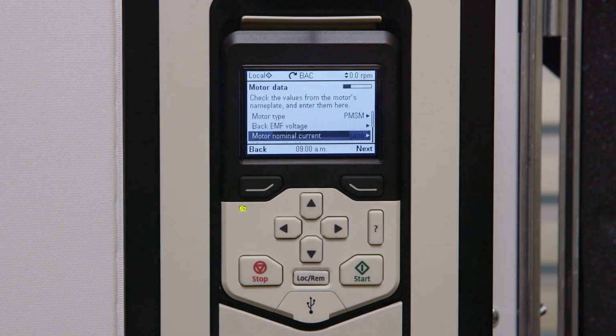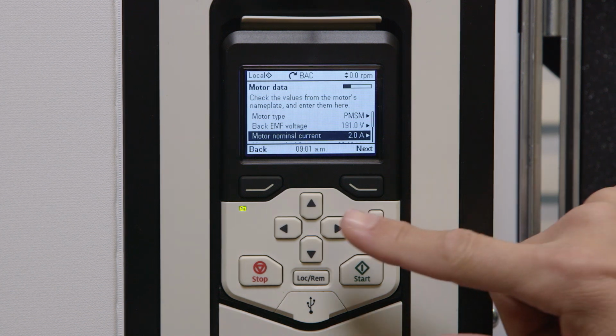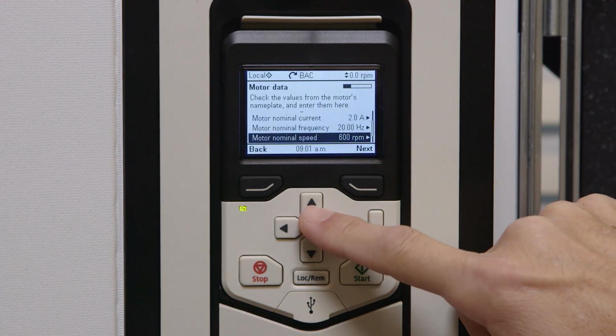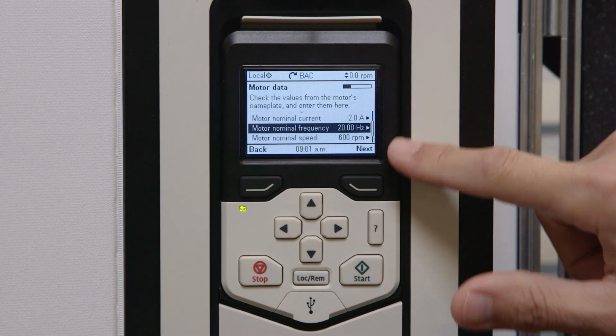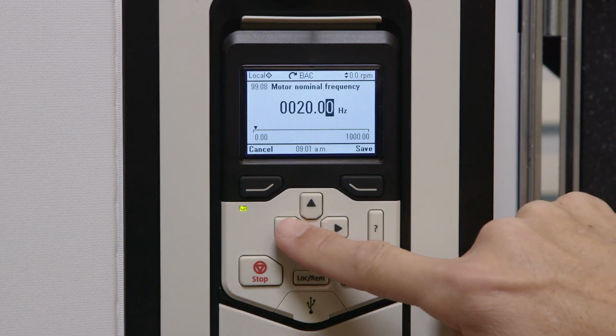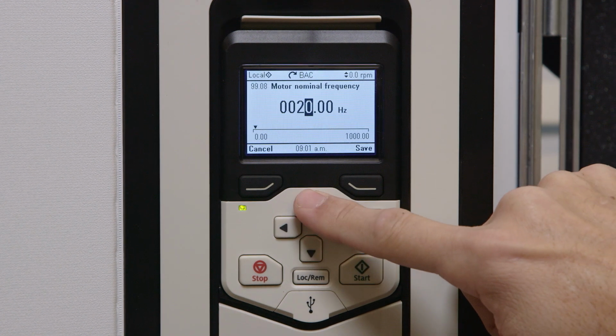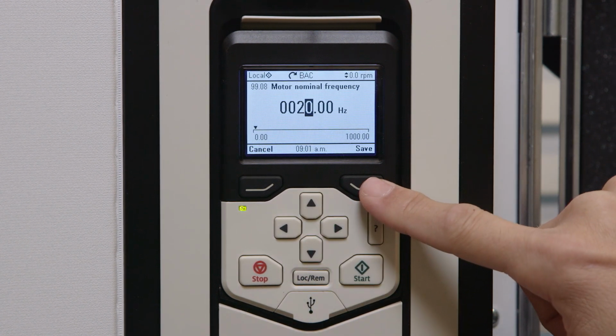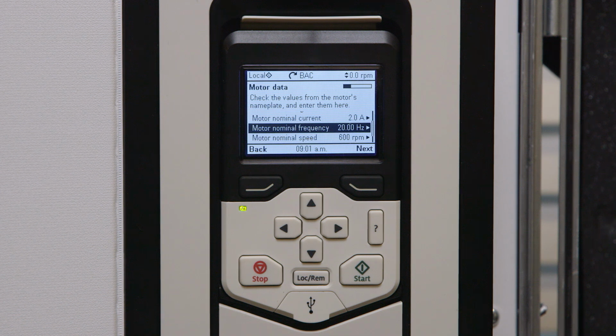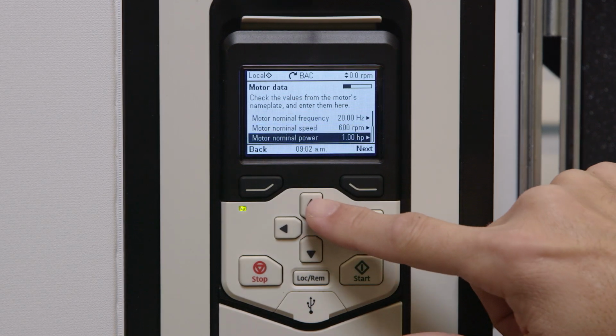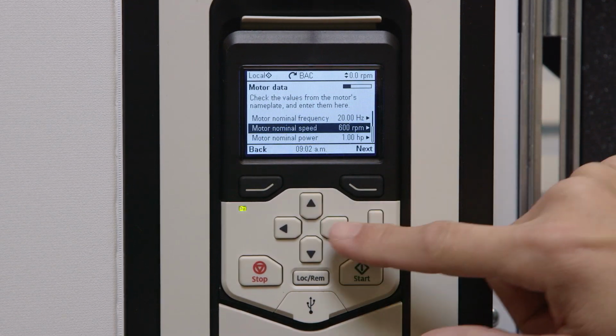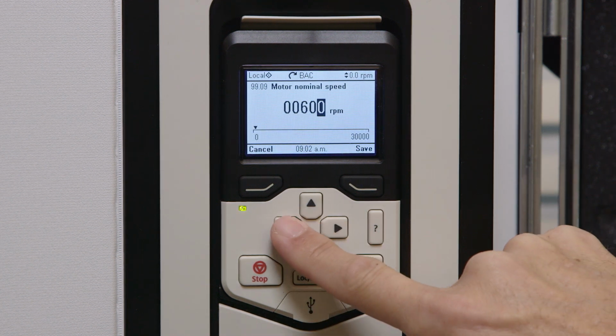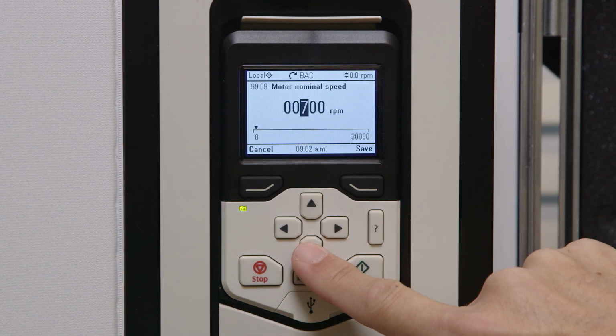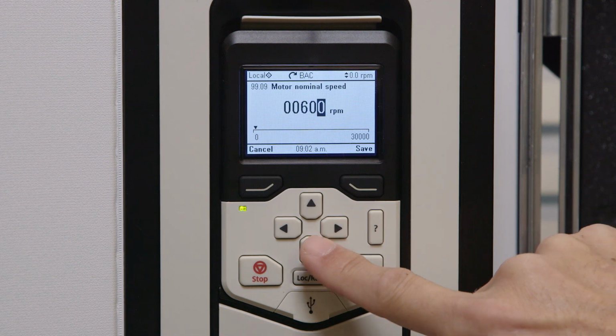Then press Save. Next, let's set up the nominal frequency for the motor. Locate the data for hertz on the nameplate and enter the number to the nearest tenth into the display. It will be printed on the nameplate as Hz. Remember again to use the value from the setup line, not the cont line. Once the data is entered, press Save. Now, let's set up the nominal speed for the motor. Enter the speed. It is the number on the nameplate printed as RPM. Remember to use the value from the setup line. Once the number is entered, press Save.